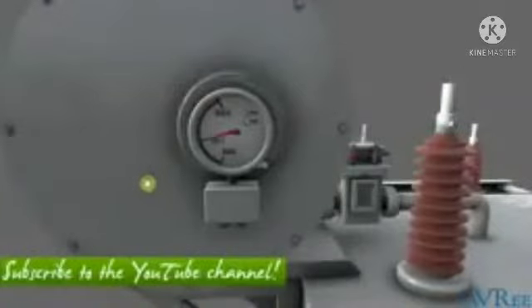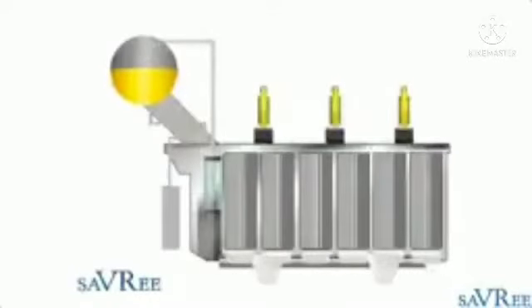So we have a form of level measurement here on the side of the conservator, but there is also an interesting component fitted below the conservator, and this is known as a dehydrating breather, sometimes called a silica breather because it uses silica gel. As the transformer heats up, the insulating liquid is going to expand, and we're going to push air out of the conservator tank, and it's going to come out through the silica breather. Let's just go up and see if I can find the holes where it comes out.